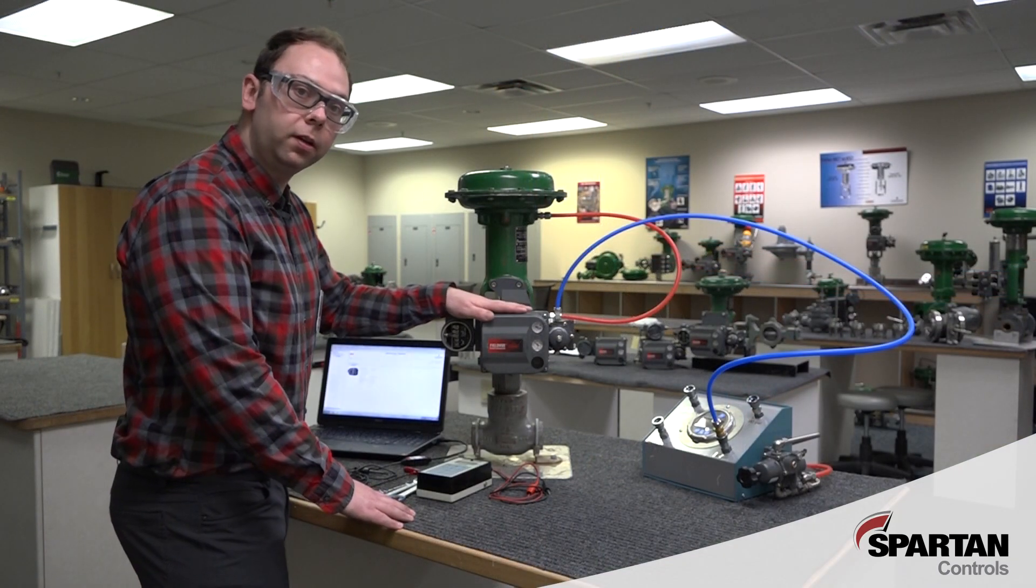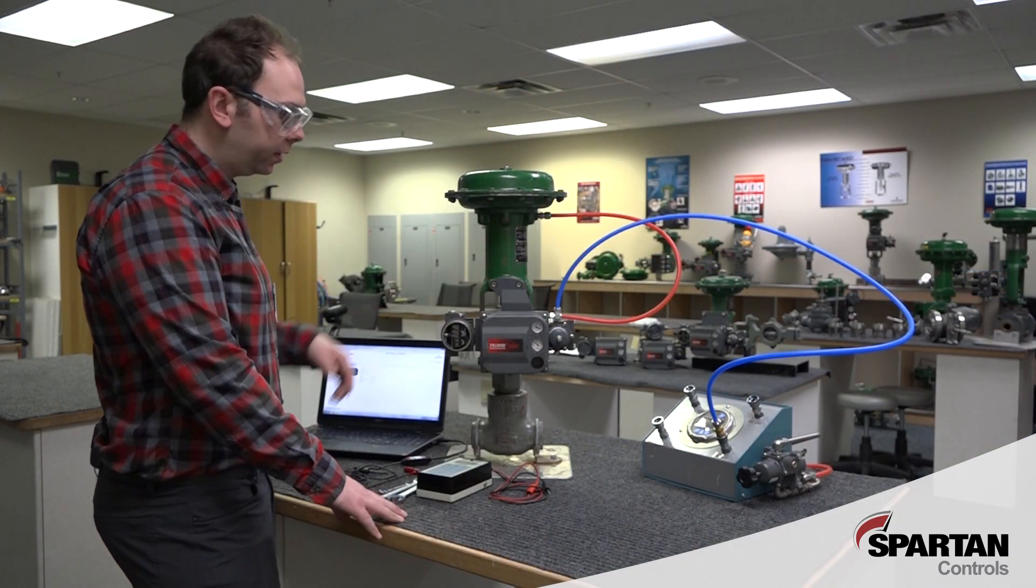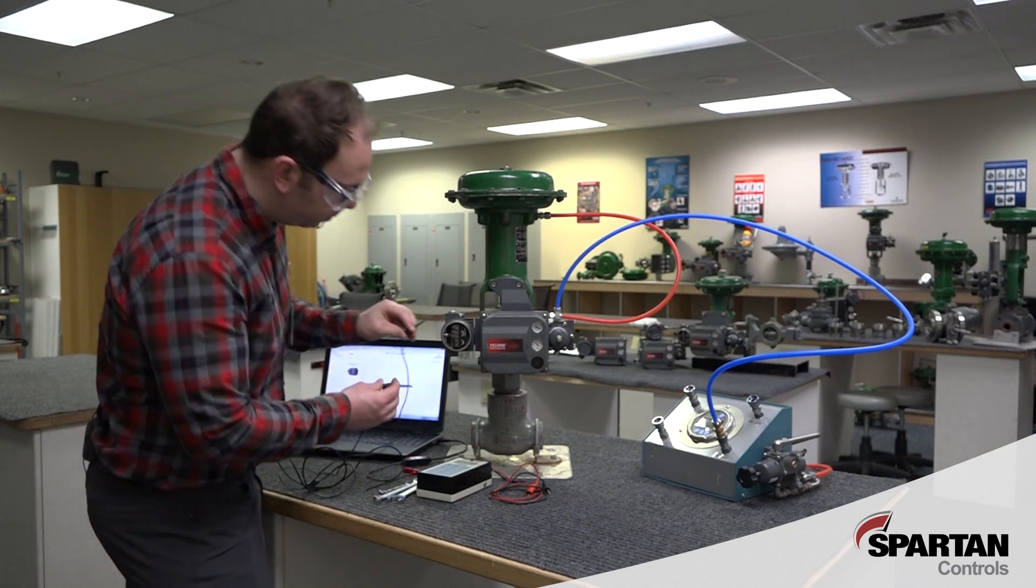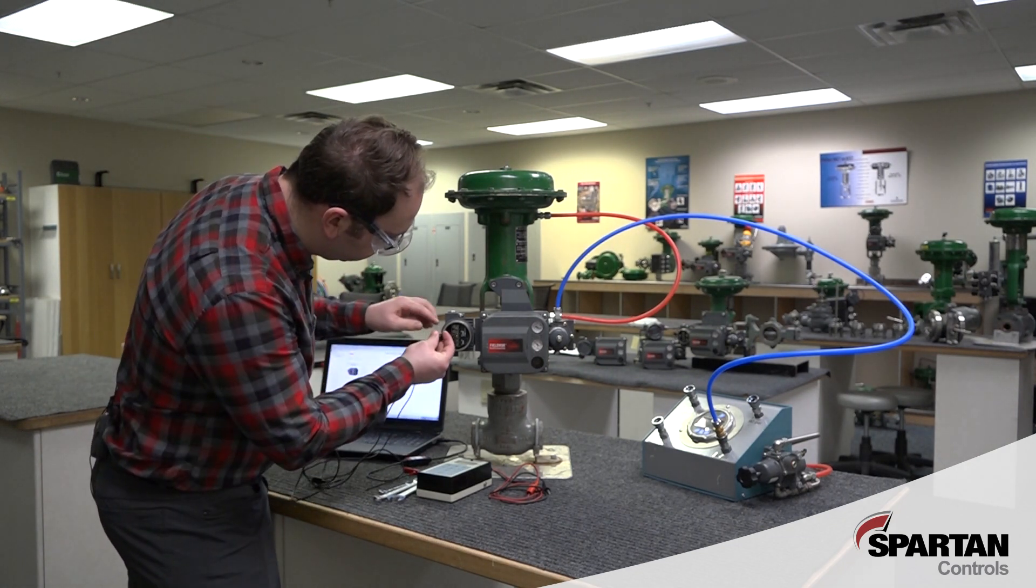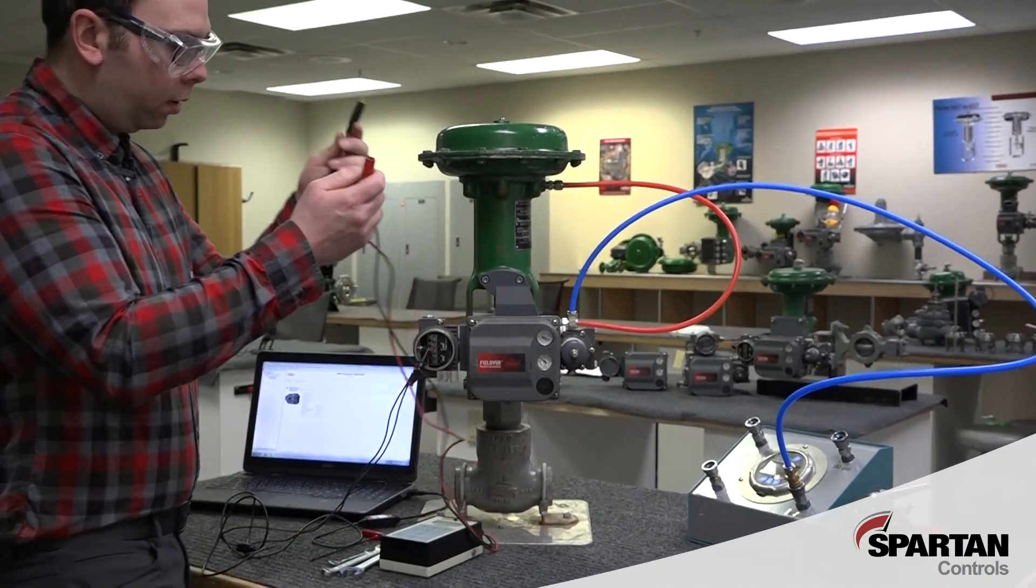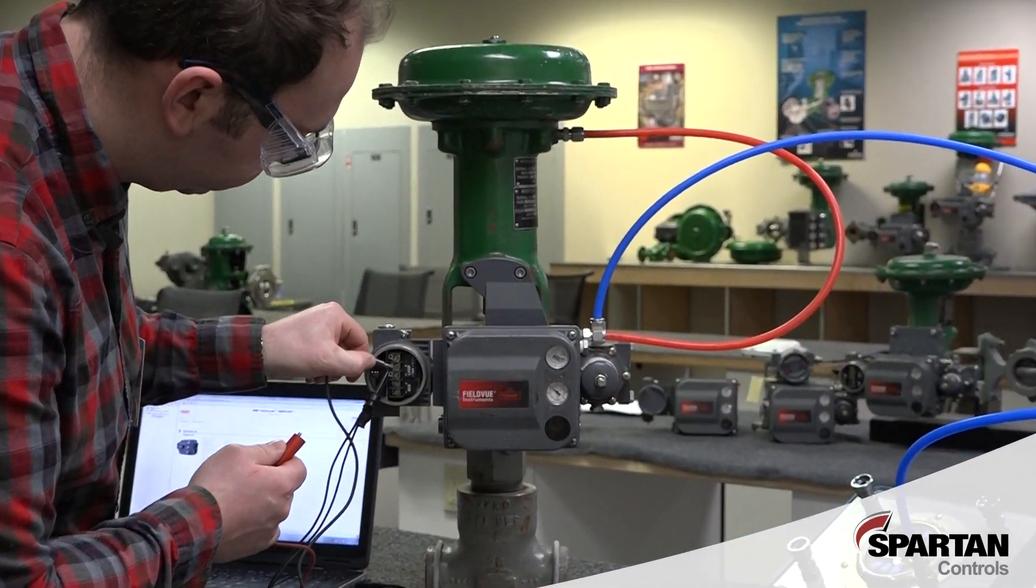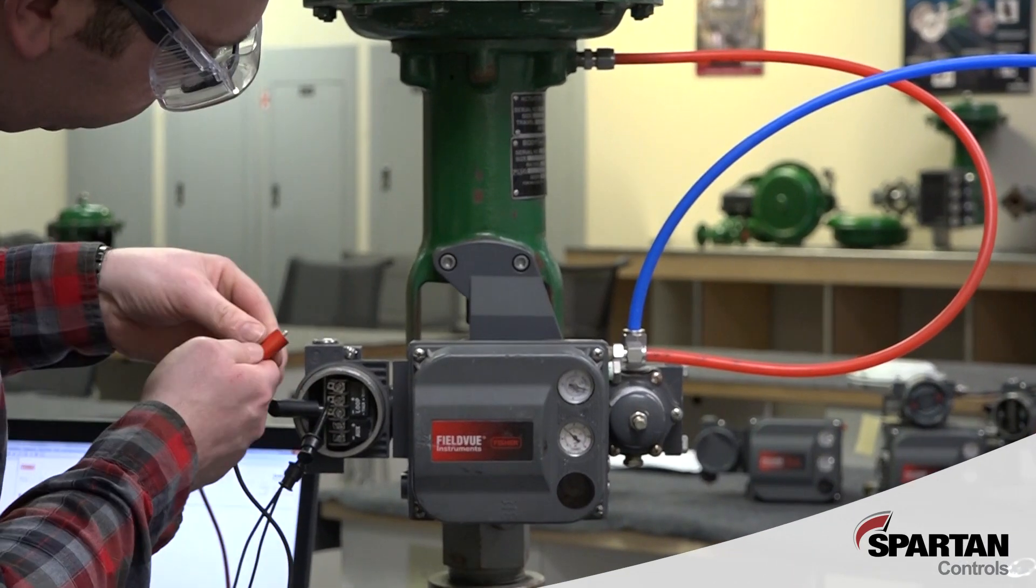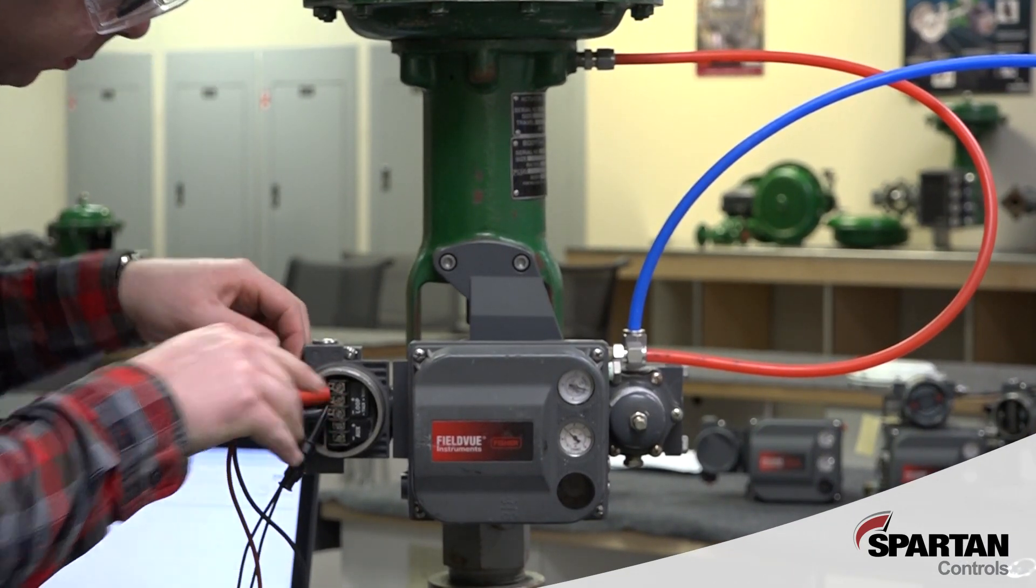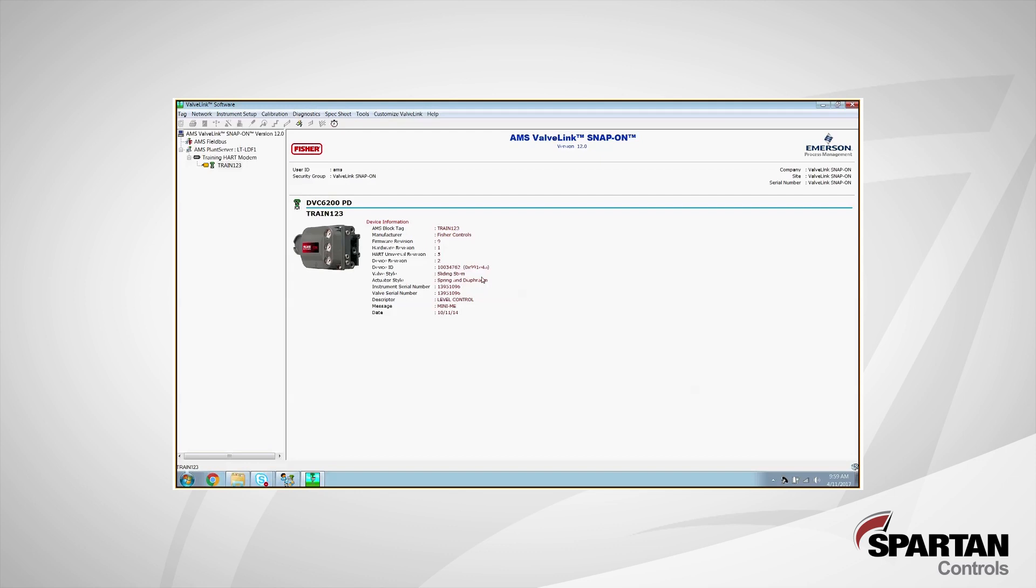With our physical installation complete, we can now connect to the DVC with our ValveLink software. For me, I'll be using a USB HART modem and a 24-volt loop calibrator. With the DVC fully connected to our computer, we can now go into our ValveLink software and start our setup wizard. The easiest way I found to do that is to right-click on your tag and go down to setup wizard.